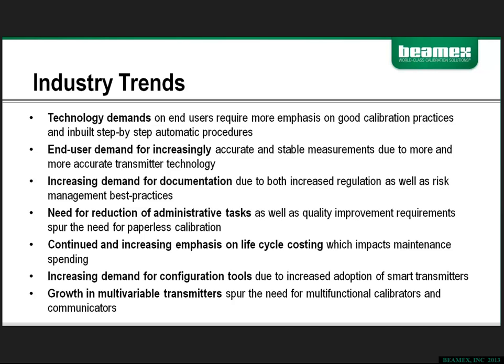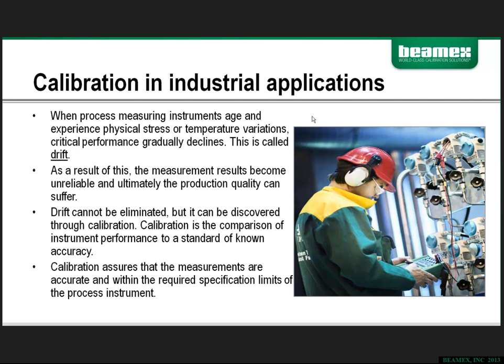Smart transmitters are requiring field communicators, which I'm sure a lot of you have noticed, and the technical demands for the new multivariable transmitters have really stressed the need for multifunction calibrators to help perform that job. So, calibration in industrial applications. What we're talking about when it comes to the process of doing this measurement, a lot of it comes back to drift. Drift is a result of age, environmental fluctuation, stress, which can be in the form of vibration, shock, or multiple other factors.